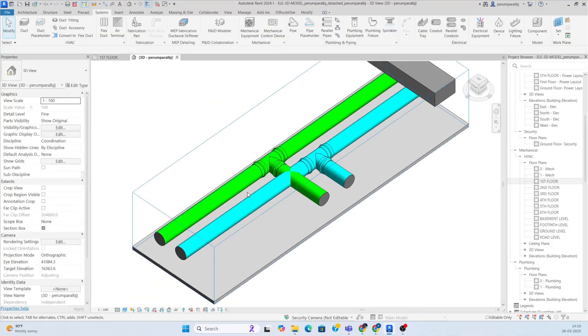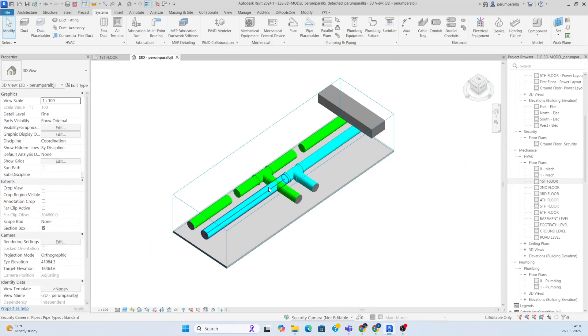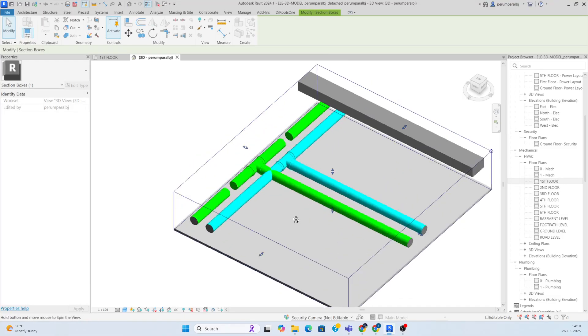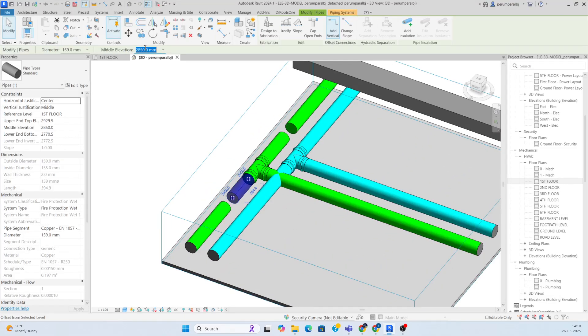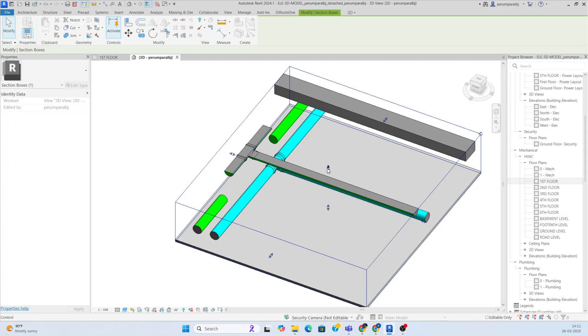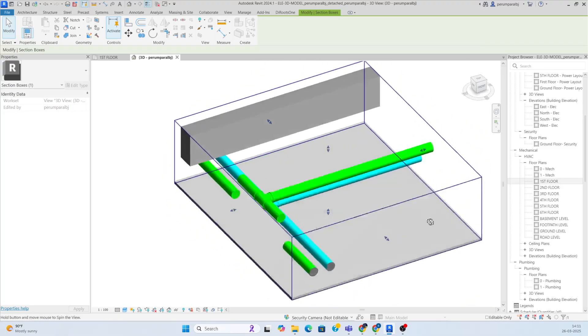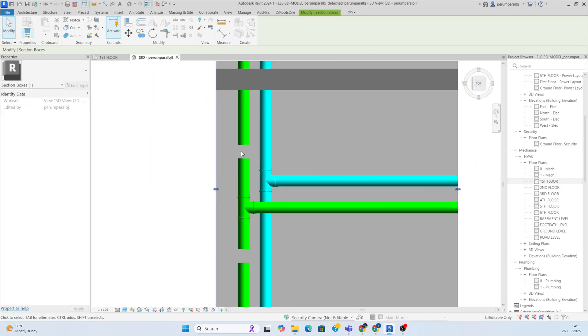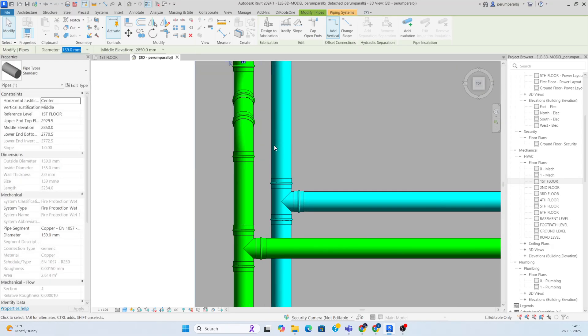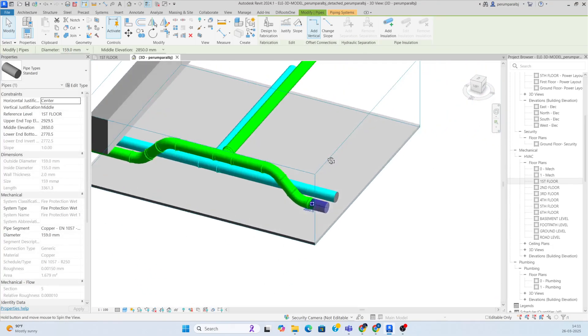Use the split command (SL) to split the pipe at the required points. Then select the split segment and raise its elevation — for example, change it to 3250. You can see the elevation is changed. Then connect the two pipe ends and the elbow bend fitting will come up automatically.